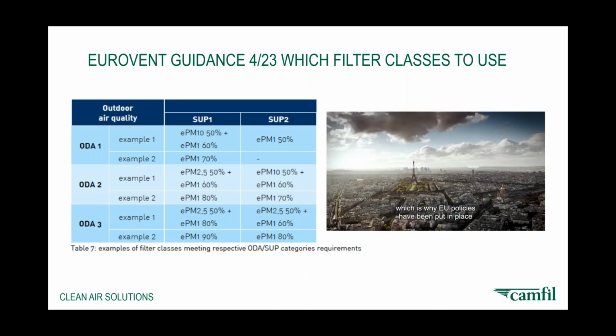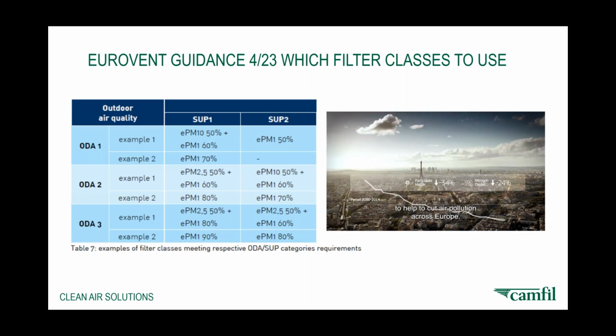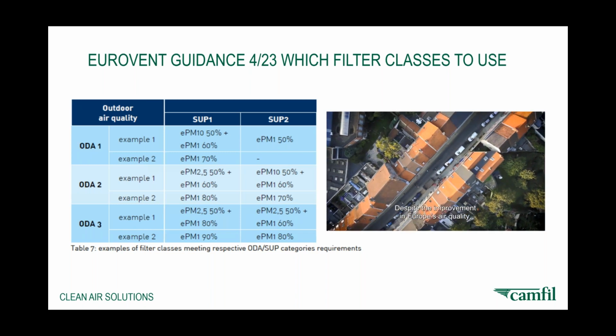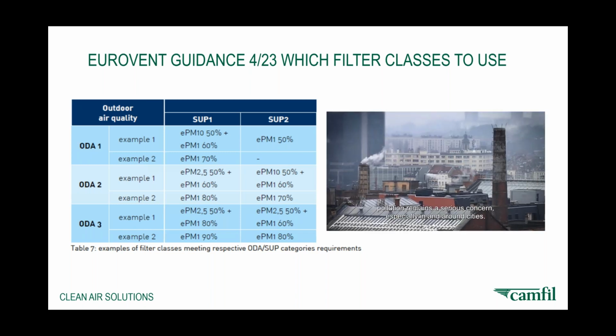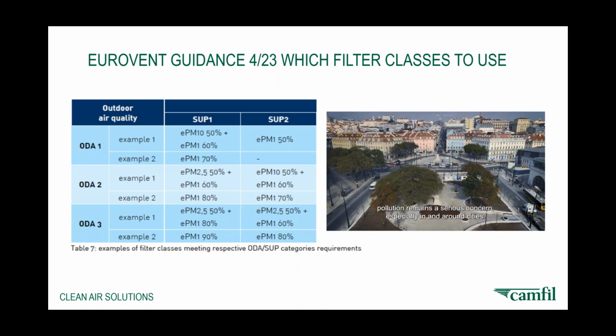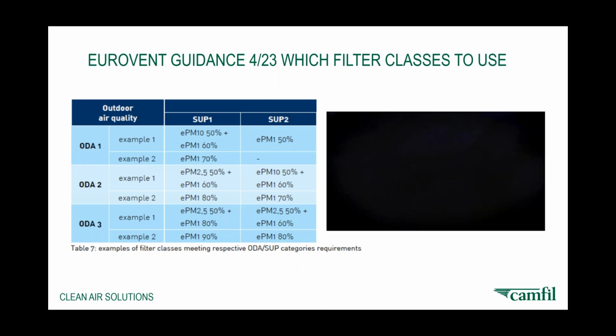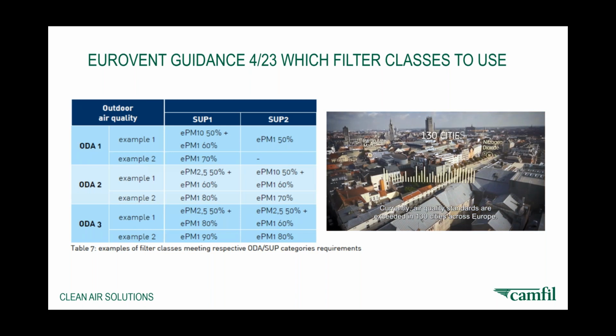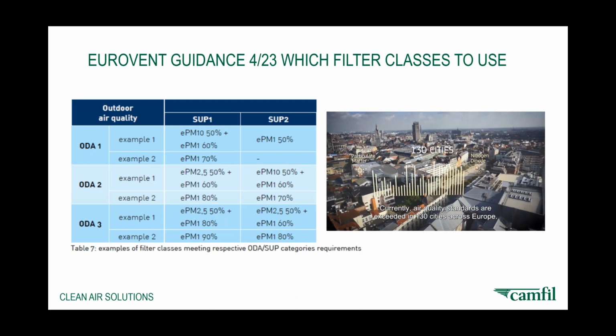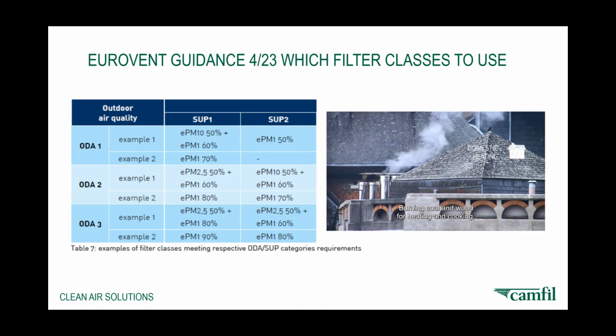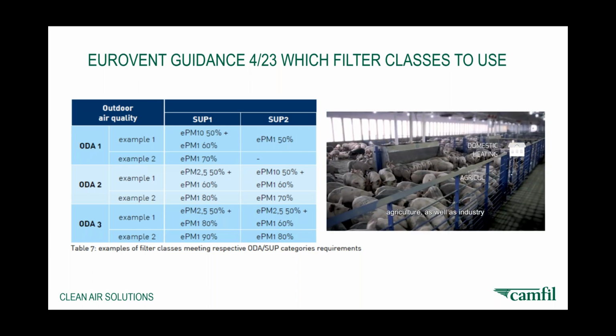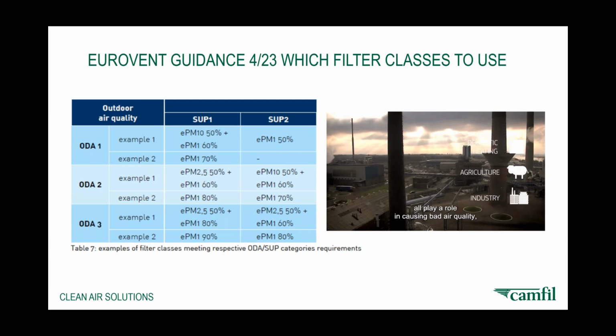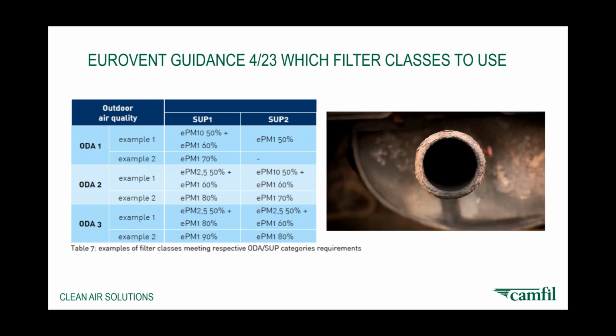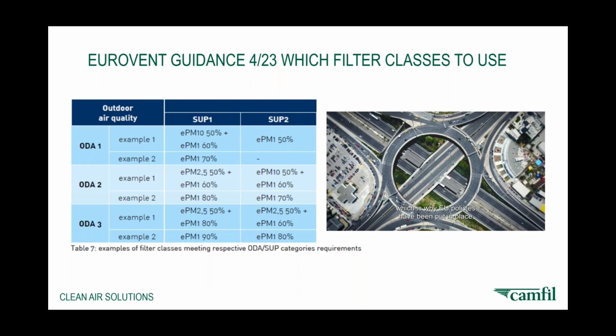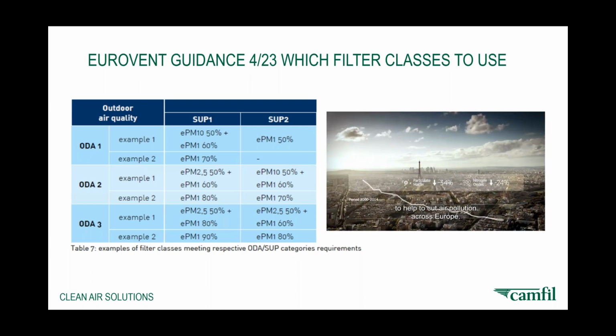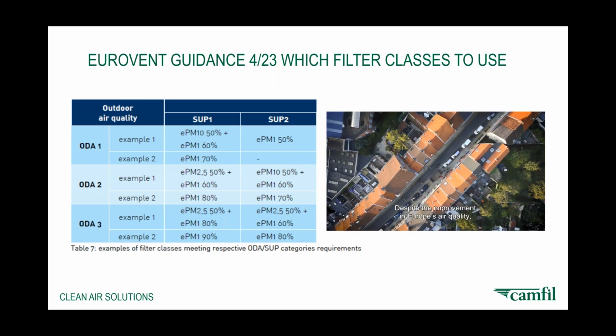So ODA is the other guidance that's given. And ODA is easy enough to define. It's based on the place where your office or building or industrial premises are located. ODA 1, for instance, would be an area where the WHO classifies it as being fairly pure air. So 10 micrograms per meter cubed for PM2.5, or 2.5 micron particles, and 20 micrograms per meter cubed of air for PM10, or 10 micron size particles. That's what they consider to be fairly pure air.